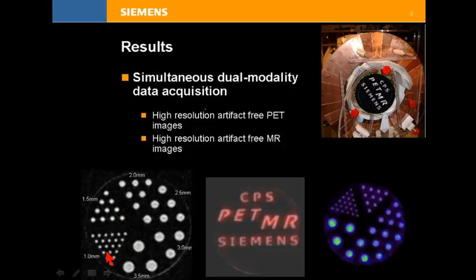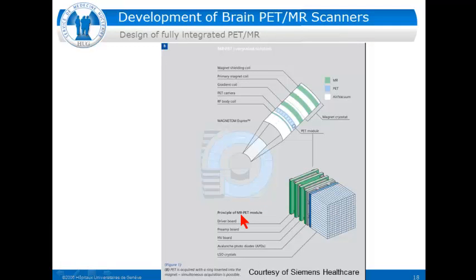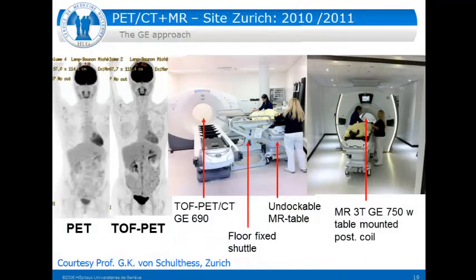This is the definitive design that Siemens now delivers: a fully integrated PET camera with detectors positioned within the gradient coils but within the static magnets of the MR system. Another approach was chosen by GE.